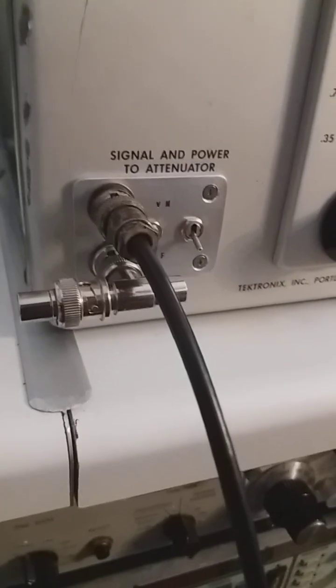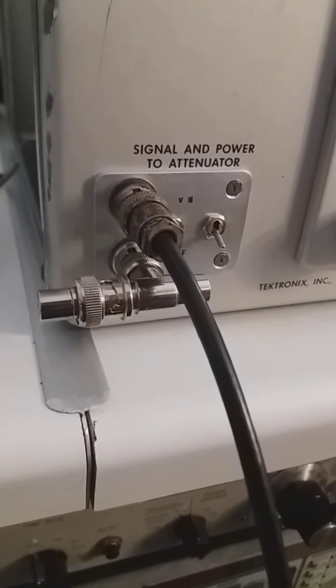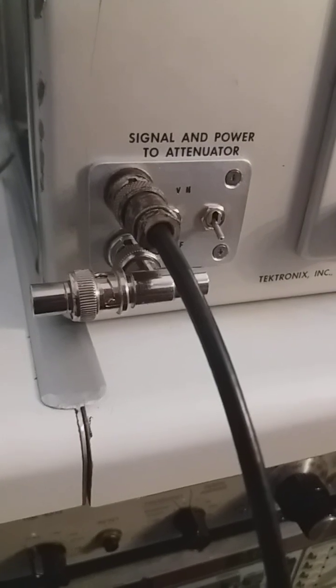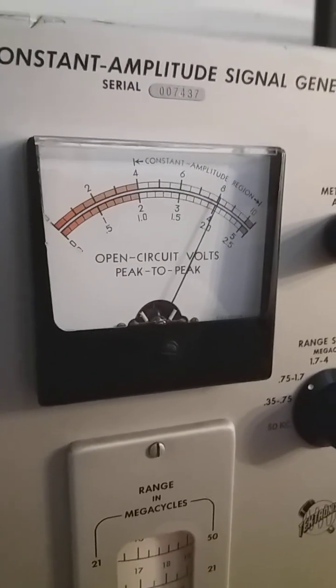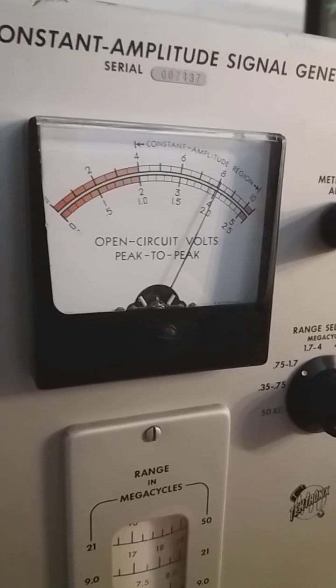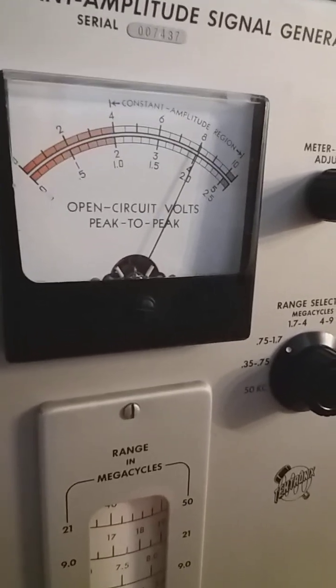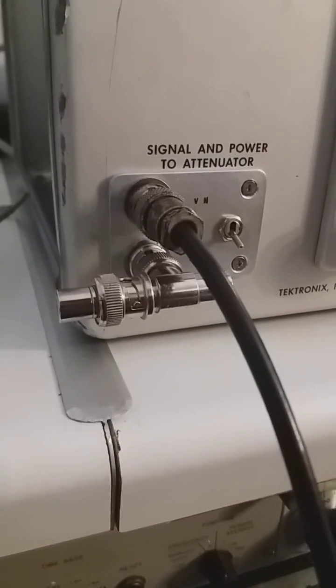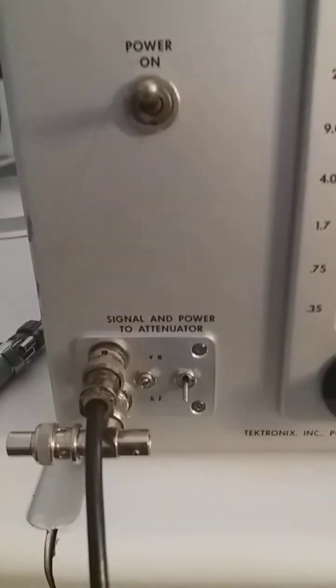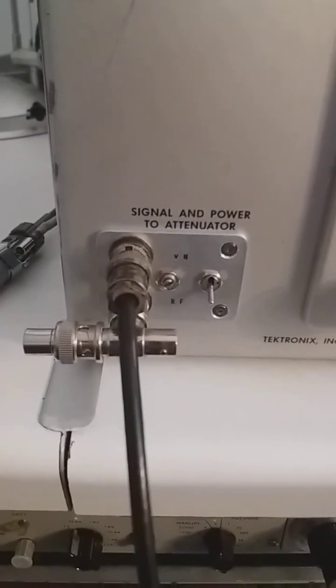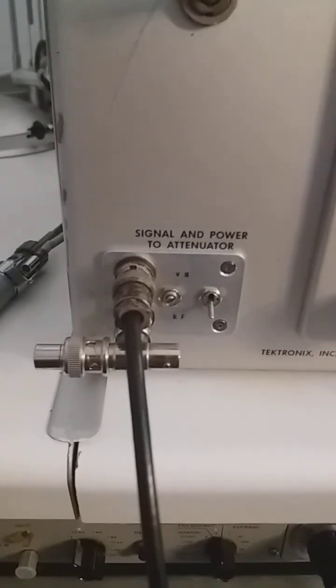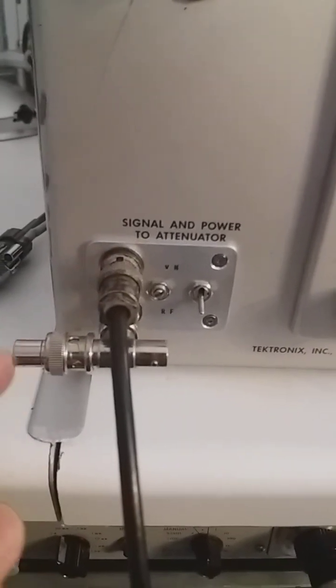It doesn't matter if I load it down to 75 ohms or 300 ohms, or just leave it completely open. It's just going to work, because the ALC is trying to keep up with any voltage drop in the oscillator and brings back the voltage to the appropriate level. So previously I have used a 50 ohms load and 75 ohms, and the same peak-to-peak voltage was appearing at the output of the generator, no matter the load that I used.